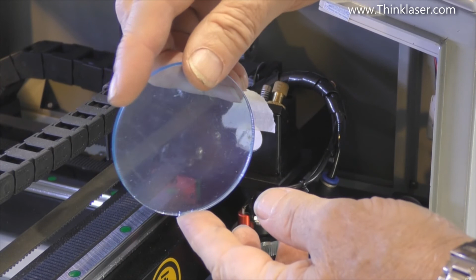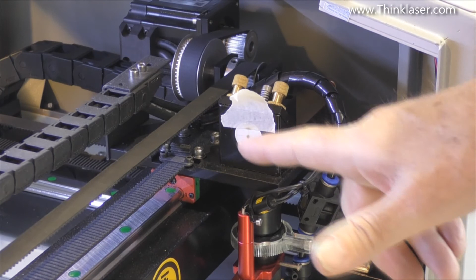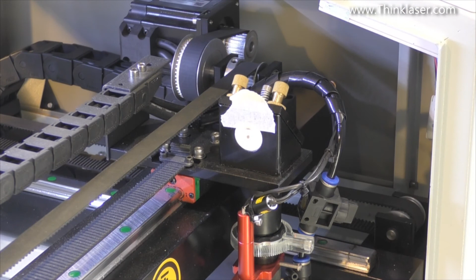Now what it does mean is that the other mirrors are very slightly compromised. Because those mirrors are twisted this way, I've got to be accurate in the horizontal plane, less so in the vertical plane. So it isn't a big issue. This one is absolutely essential. Now it is very, very slightly, maybe half a millimetre out of position in this direction. But again, because this mirror is tipped this way, I can afford to be very slightly out in this horizontal direction. And so I'm not going to go hunting any further for the problem at mirror 3. That's as good as I can get.